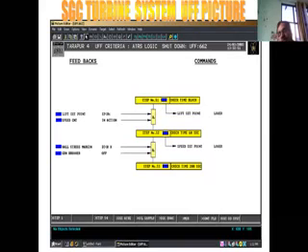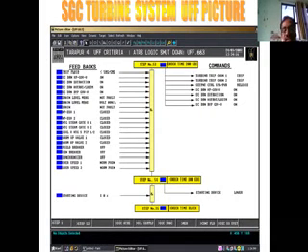We will desynchronize the machine. Then we will cut off the steam of the turbine. After that, if it is a long shutdown, then we'll go for cutting the lube oil, then control fluid, then lube oil. Just reverse it.